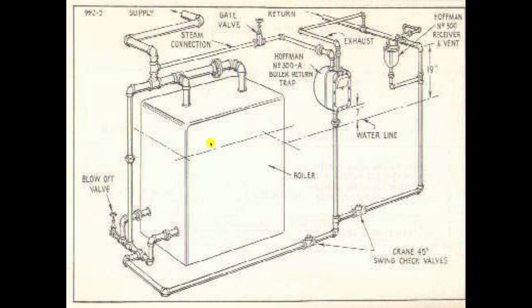But if the pressure should go above one half pound, the boiler pressure shoves back against the check valve and closes it. Now over here there's suddenly enough weight to open this check valve, but we can't get the inboard check valve open because the excessive boiler pressure is keeping it closed.